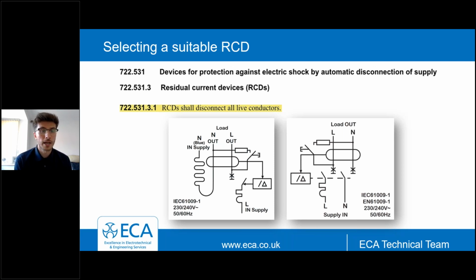So we're going to move to now selecting a suitable RCD. A very topical point of conversation in general, I think, when looking at EVs and maybe other renewable technologies at the minute, but obviously focusing on EVs today and selecting a suitable RCD. So within page 327 of BS 7671, regulation 722.531.3.1 tells us that RCDs shall disconnect all live conductors.